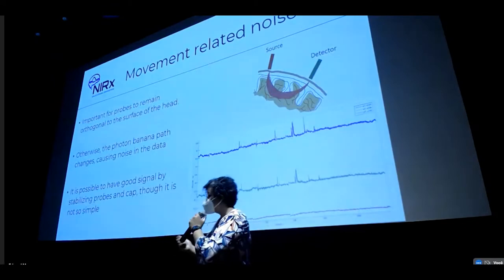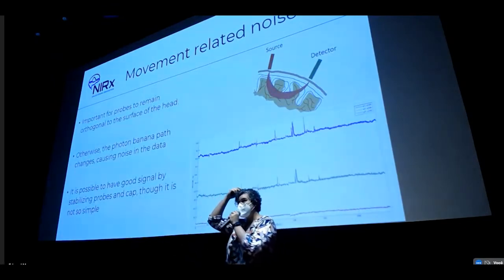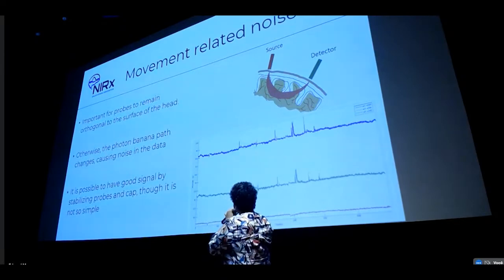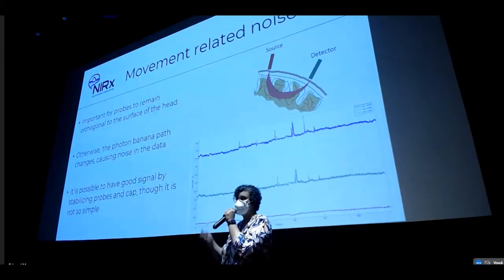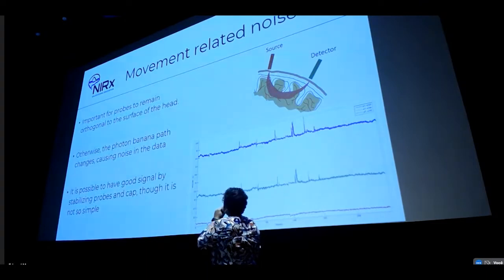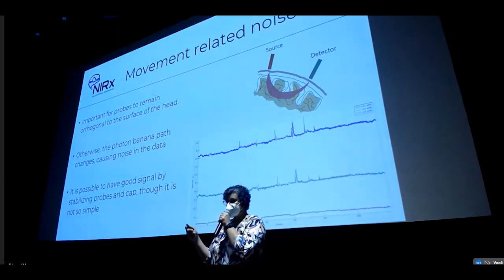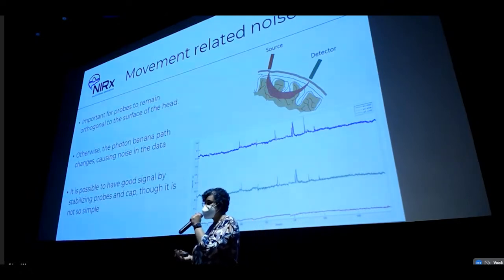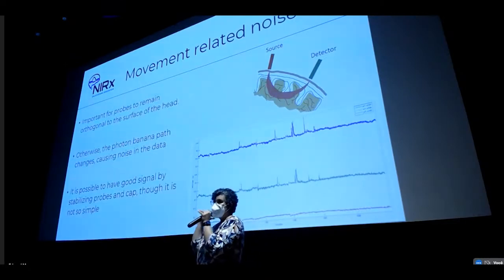Another blocker is environmental light. Usually lab or hospital lighting is fine — you'll be able to capture the fNIRS signal. But if you go outside in very bright sunlight, you will definitely see environmental noise in your data, because sunlight includes near-infrared. You should use an overcap to block the light. For example, when doing experiments with infrared cameras in a gait lab, the infrared was interfering with fNIRS data, so aluminum foil caps were used to reflect it. Also, movement of the optodes on the skull causes spikes in your data, and light leakage causes a baseline shift. These movement-related noise issues can be avoided by proper cabling, proper head fit, and movement control.